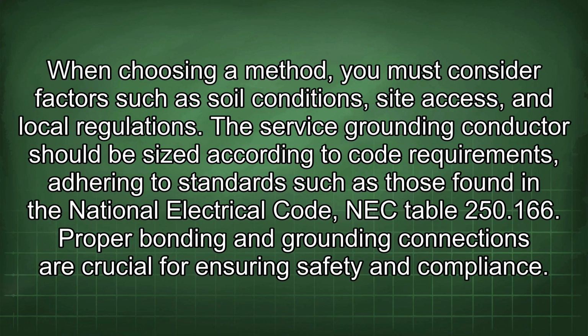When choosing a method, you must consider factors such as soil conditions, site access, and local regulations. The service grounding conductor should be sized according to code requirements, adhering to standards such as those found in the National Electrical Code, NEC Table 250.166. Proper bonding and grounding connections are crucial for ensuring safety and compliance.